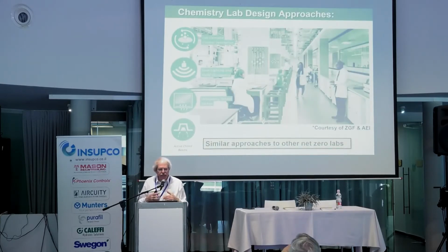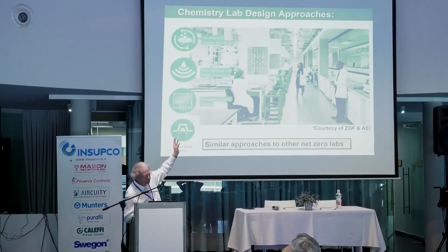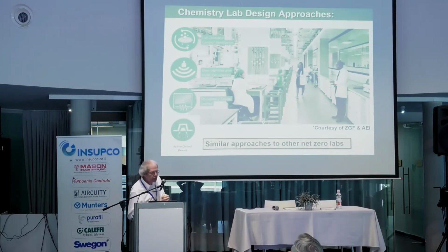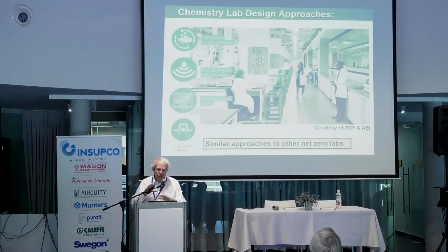So again, from a chemistry lab standpoint, what were they doing? Again, some of the same things we talked about, a demand-based system we talked about earlier. They're using dual lighting and HVAC occupancy controls, using sensors on the sashes to reduce the sashes and lower the velocities of the fume hoods, using chill beams again, like we talked about. So again, you see that as a common theme to be able to decouple the cooling from the airflow. So we reduce the airflow down, have the airflow be internally cooled in the lab, so we're not bringing this massive amount of airflow from outside to cool or heat it and bring it into the lab. Just use a smaller amount of airflow in the lab and then cool with devices in the lab, chill beams, fan coils, those devices.